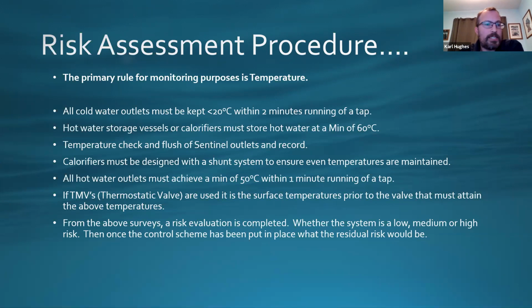As part of the assessment, you take a temperature and you flush the sentinel outlets and you record the temperatures of those. So maintaining your less than 20 degrees for your cold water, and then again your hot water has got to be above 50 degrees within 1 minute of turning on the outlet. A lot of places now, and it's one thing that we come across a lot, have mixer valves. So you take a temperature from the surface pipework of the incoming hot water to the TMV, which is designed to blend the water to around about 40 degrees.